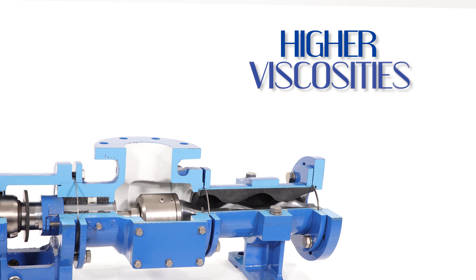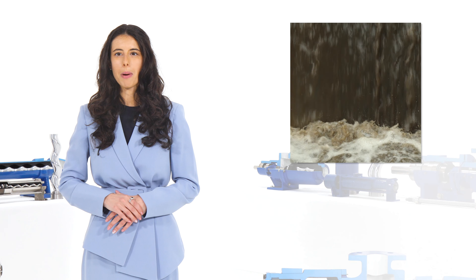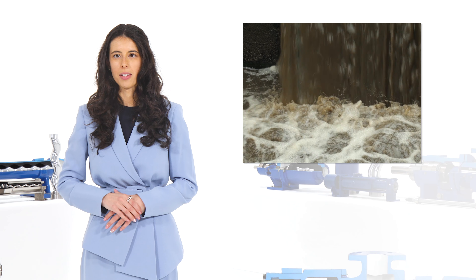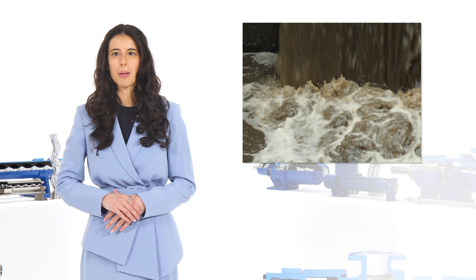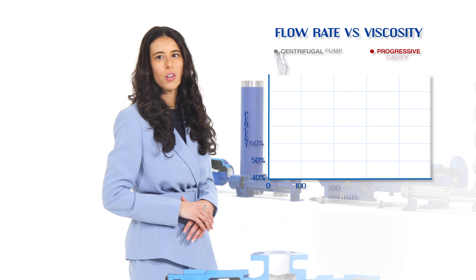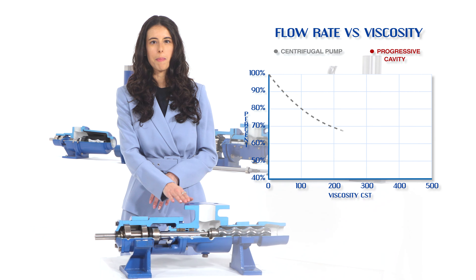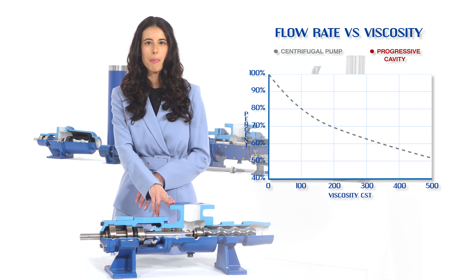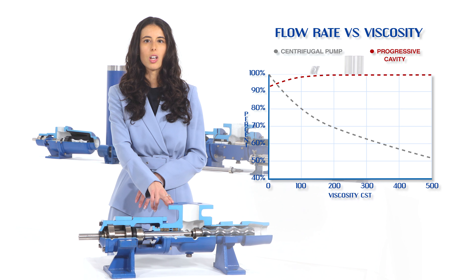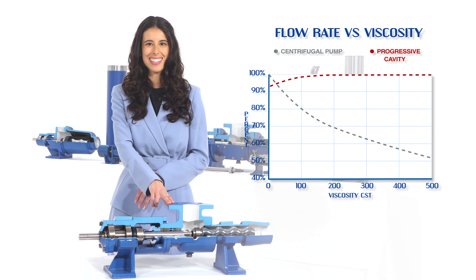Higher viscosities than water. When the liquid being pumped has a thicker viscosity than water, the progressive cavity pump is the right choice. When compared to centrifugal or other types of positive displacement pumps, a PC pump can handle much higher viscosity with ease due to its low internal velocities and large cavities.